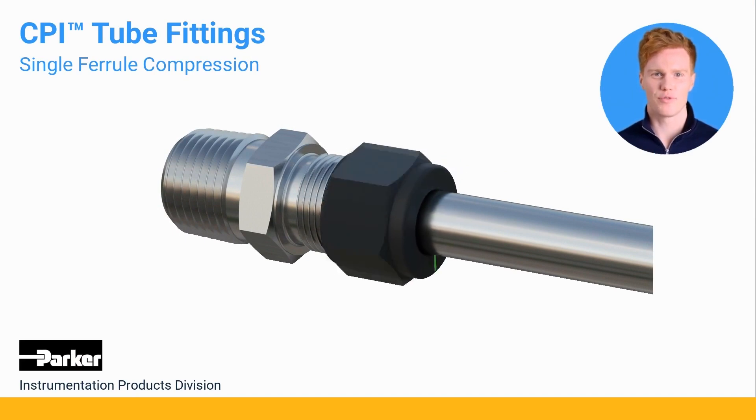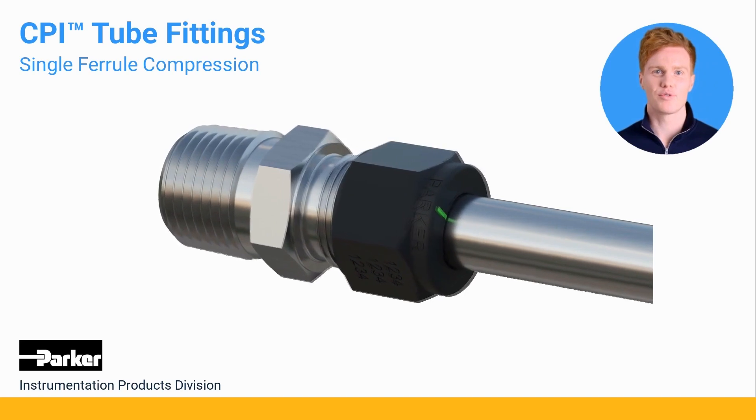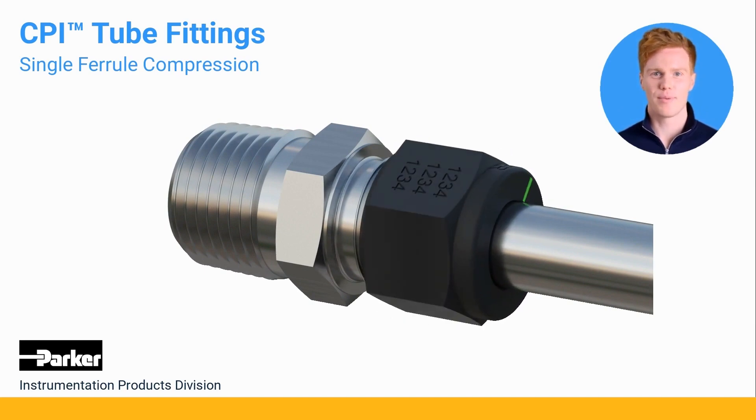To assemble the CPI tube fitting, insert the tube into the fitting body until it comes to a stop. Tighten the moly-coated nut to finger tight. You will then need to use a wrench to tighten the nut one and one-quarter turns, as shown here by the green line. Parker offers a small-bore expert training program to fully certify people using the CPI tube fitting.